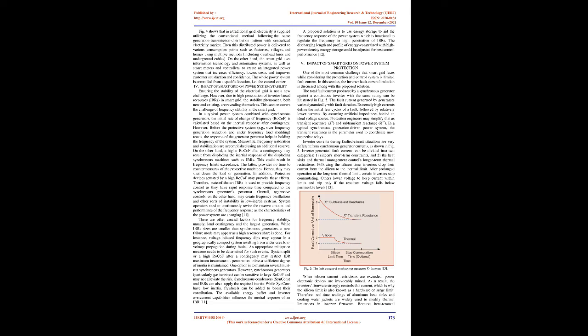However, before the protective system, e.g., over-frequency generation reduction and under-frequency load shedding, reacts, the response of the generator governor helps in holding the frequency of the system. Meanwhile, frequency restoration and stabilization are accomplished using an additional reserve. On the other hand, a higher ROCOF after a contingency may result from displacing the inertial response of the synchronous machines with IBRs. This could result in frequency limits being exceeded.